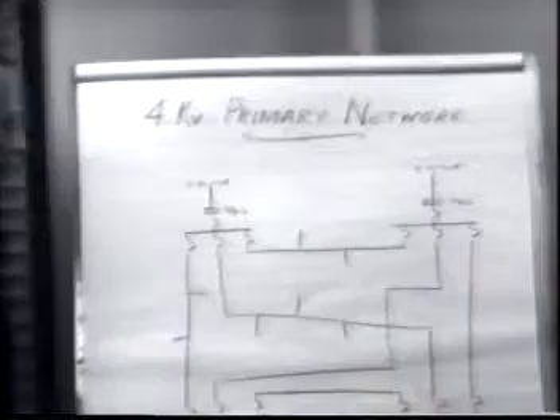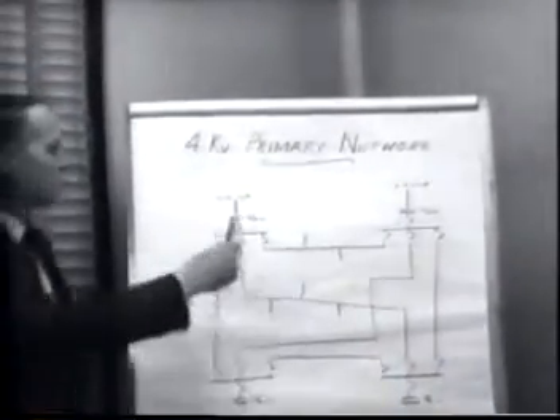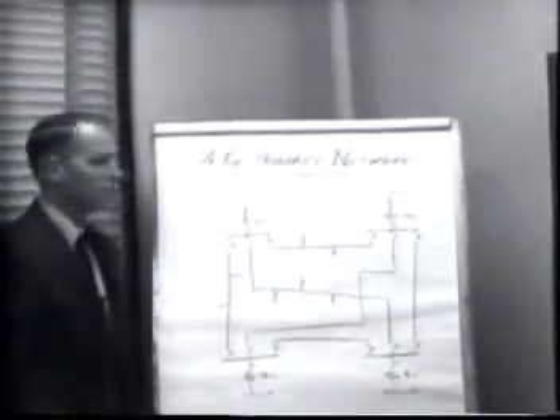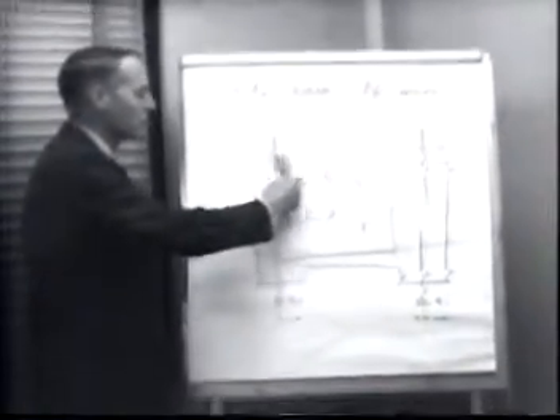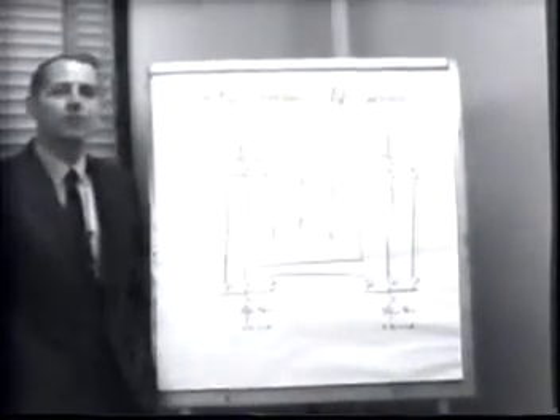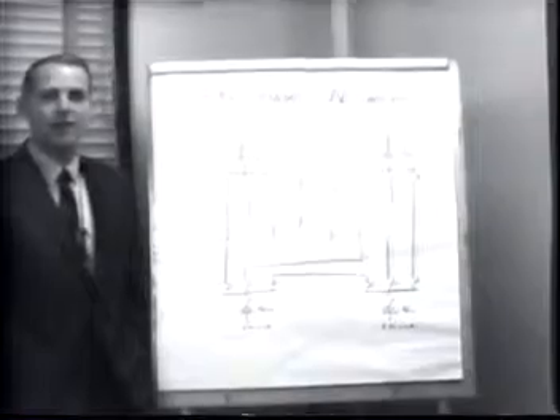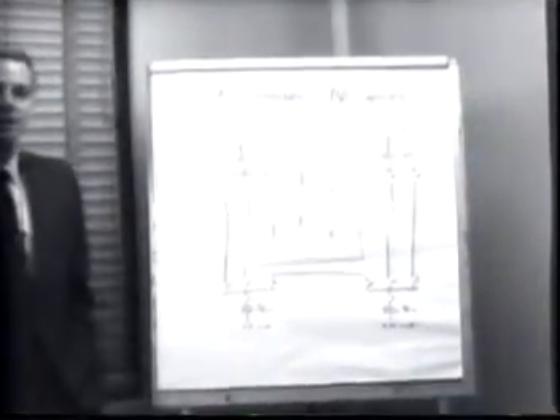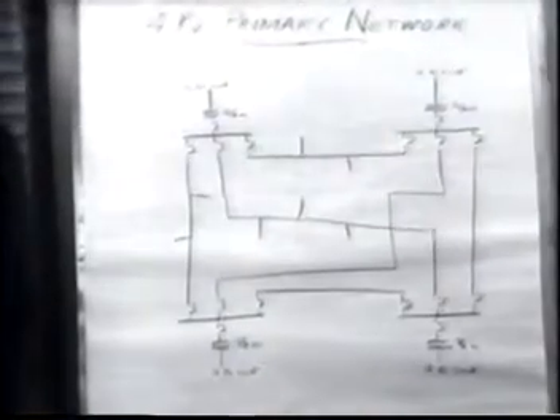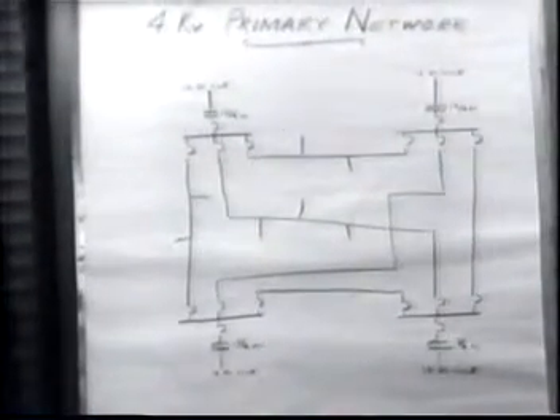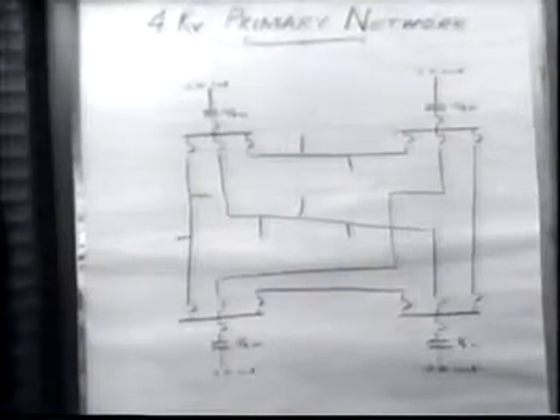And since from a transmission standpoint the different sources would feed the given substations, the transformers themselves were sized so that you could take any one of the transformers out for maintenance or because of equipment failure, and the tie lines to the adjacent substations would provide enough capability to feed the load from this substation. On a given circuit you would have two means of feeding each major load area. So this was a system that provided a great deal of reliability to electric service.